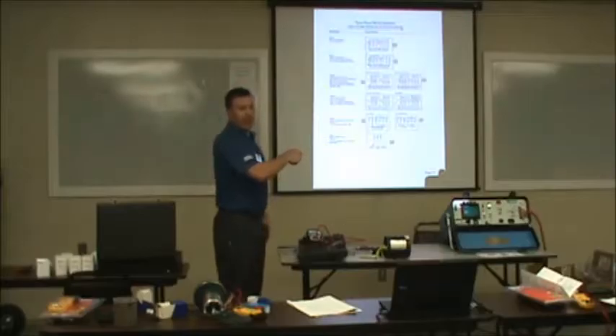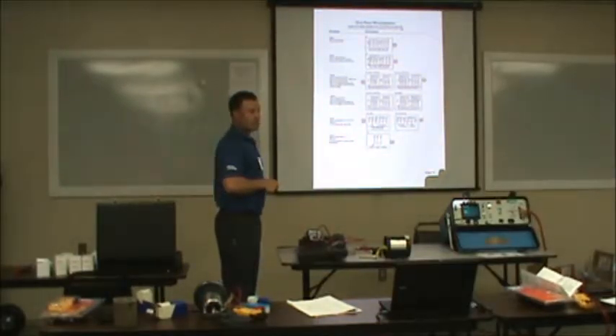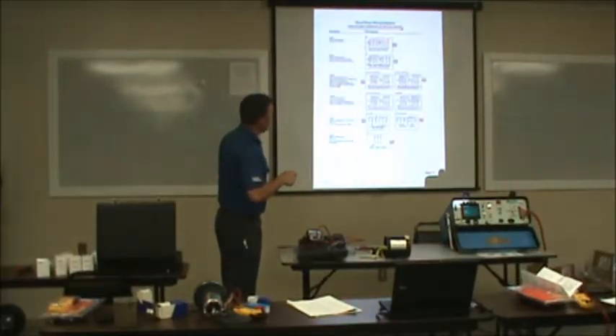low voltage is two Ys. We're going to make one right there. The other one's internal. The manufacturer puts it inside the motor, and when we rebuild the motor, we put it inside the motor. When we're running on high voltage, you've got one wire going to each lead. You're going to tape those two, one of those two together.